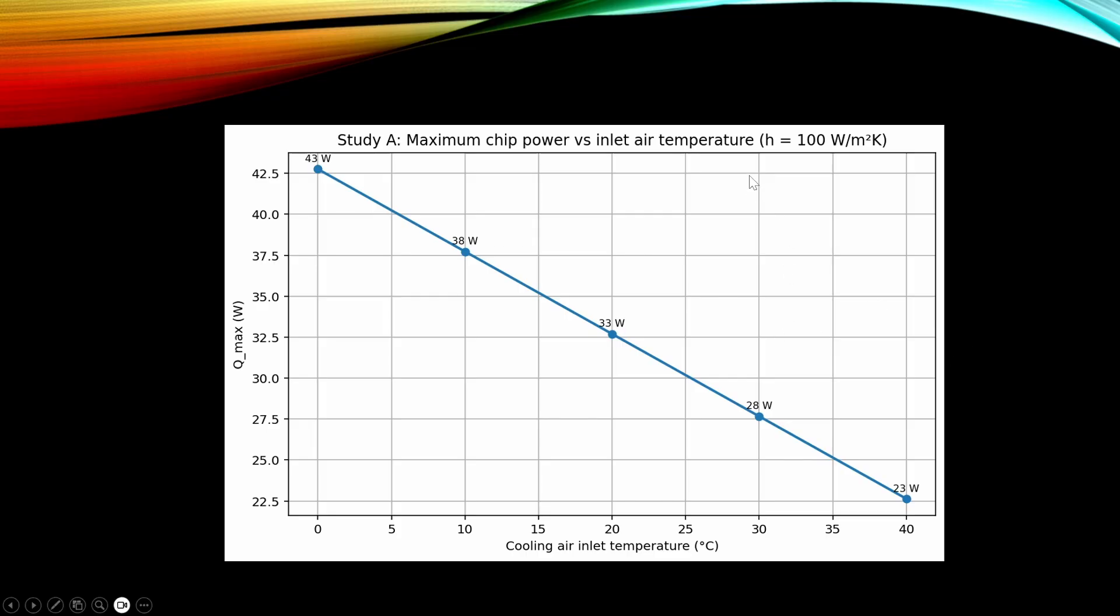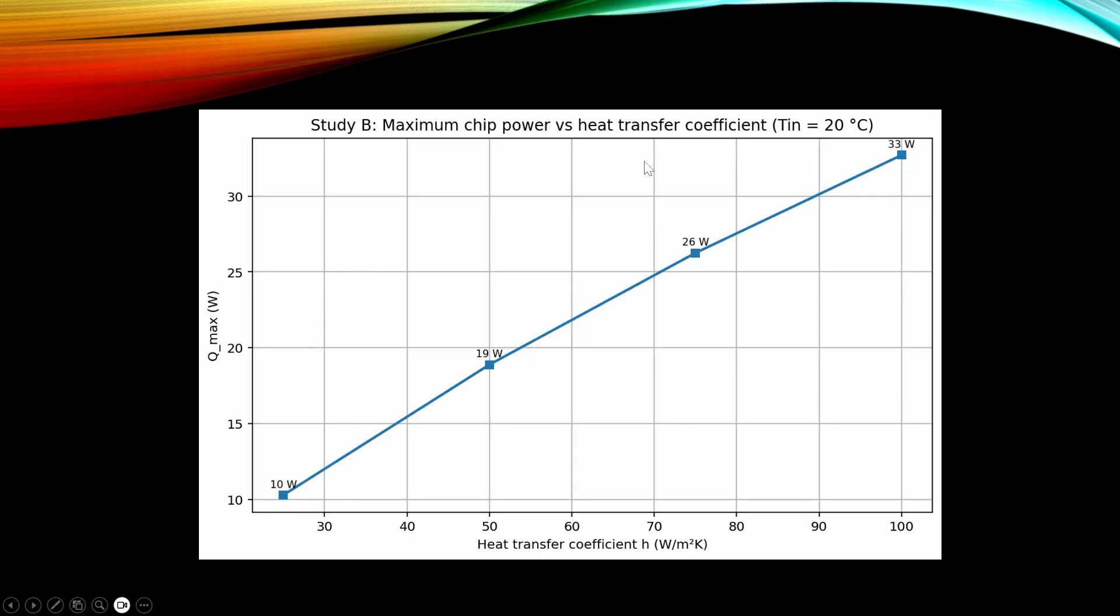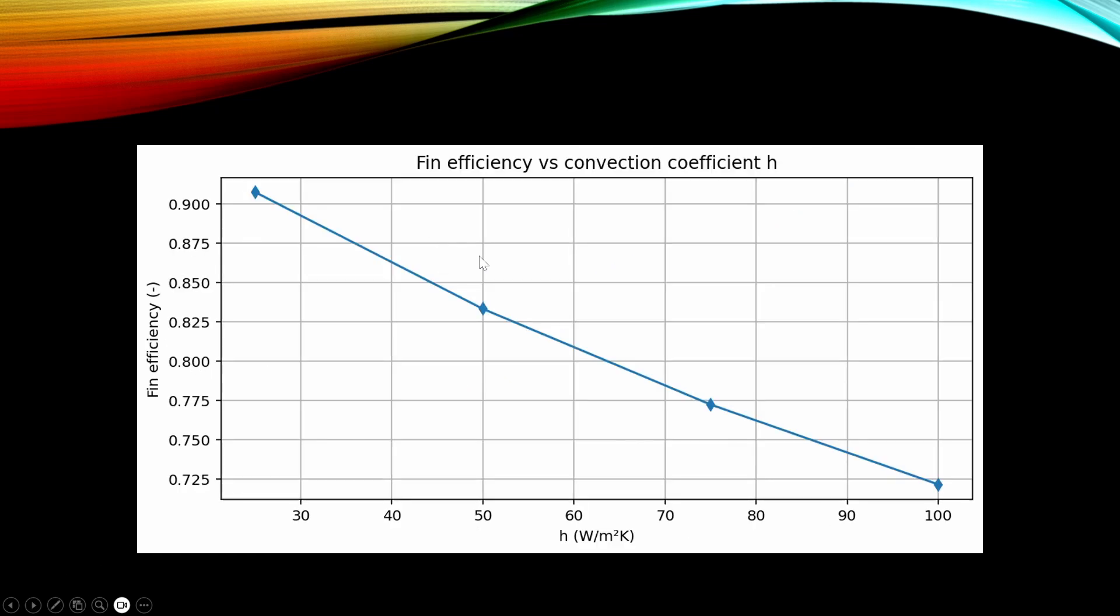And for example here we see a plot of maximum chip power as a function of inlet cooling air temperature, and this was calculated using a convective heat transfer coefficient. And in this next one we see the maximum chip power as a function of this heat transfer coefficient. Here this heat transfer coefficient is from 25 to 100 watts per square meter Kelvin. And on y-axis we have this maximum power. Here is a function of fin efficiency as a function of heat transfer coefficient. And because the material was aluminum, these fin efficiency values are in a typical range for aluminum.